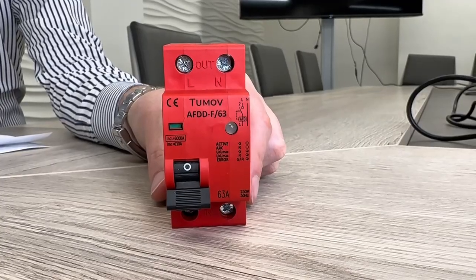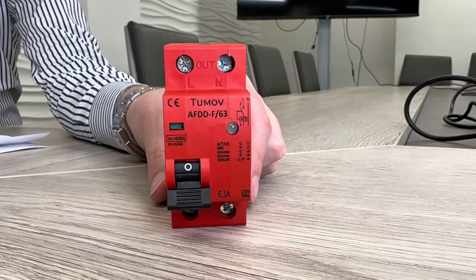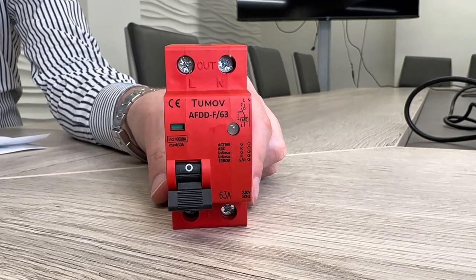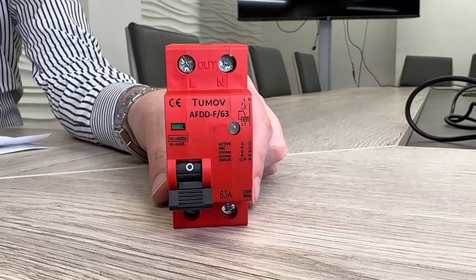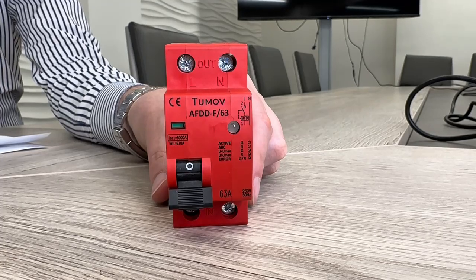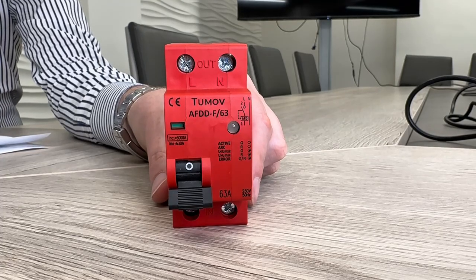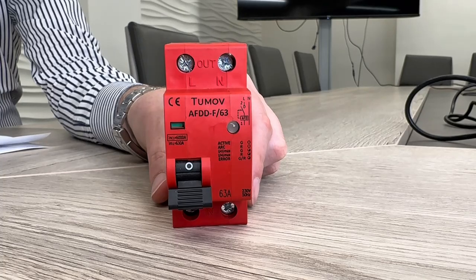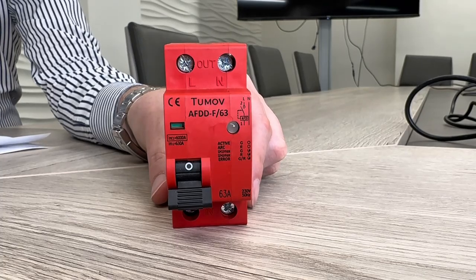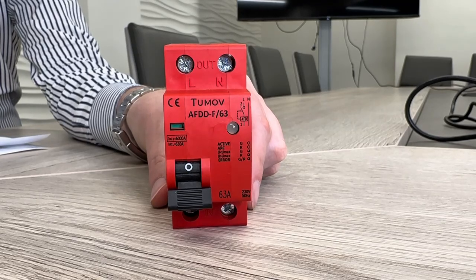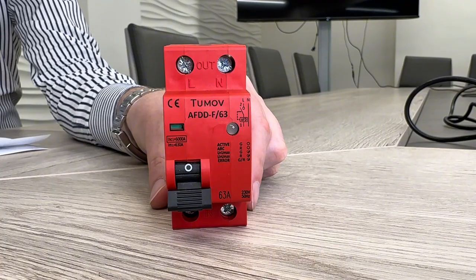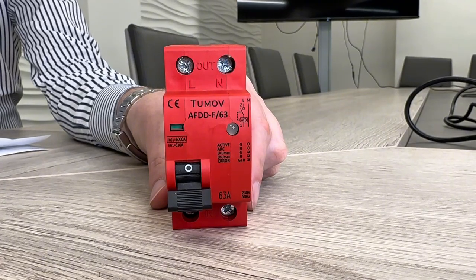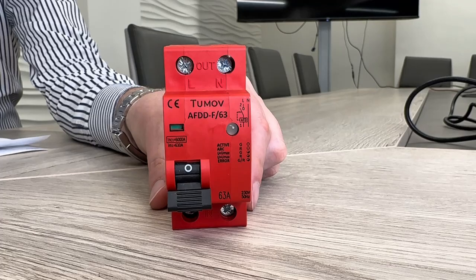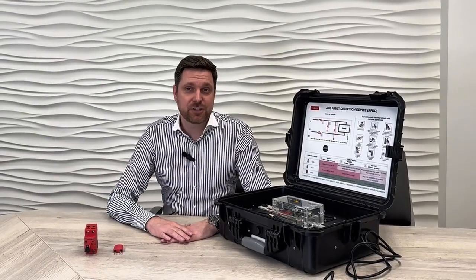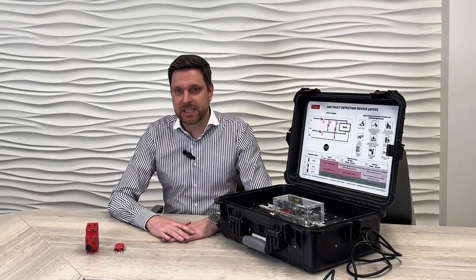Some technical details. The AFDD TUMOV fully complies with the IEC 62606 standard. Arc detection is provided by a multi-factor, multi-stage algorithm. 35 mm DIN rail mounted. Trip cause LED always on. A single device with a rated current of 63 amps is sufficient to protect an apartment, office, or house up to 150 square meters. Special bonus. A special test unit is included in the AFDD TUMOV kit.